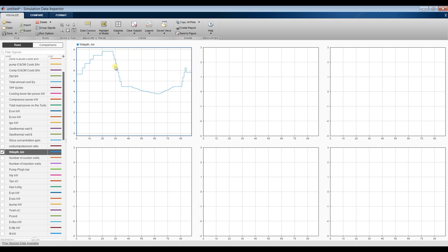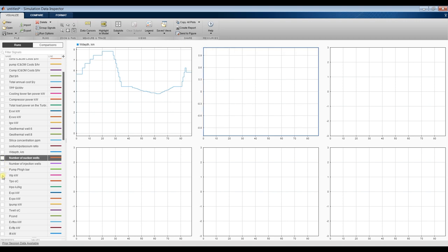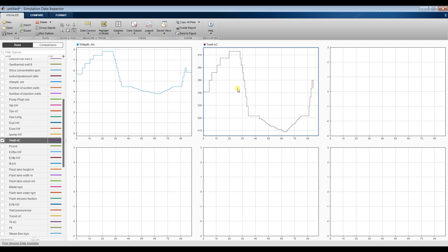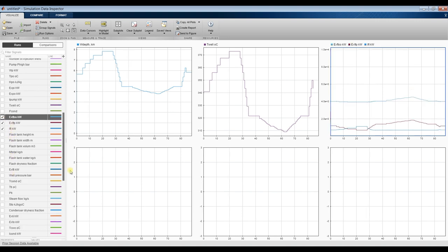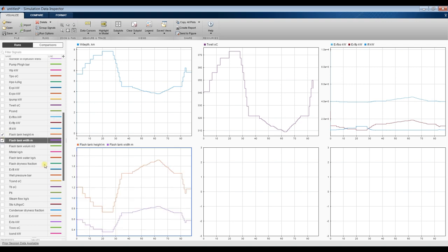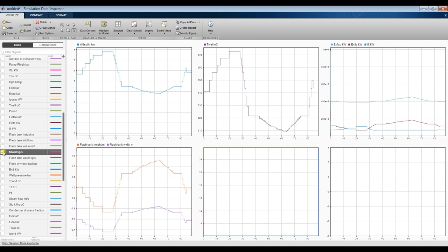Well temperature variation is visible as pressure changes up and down. Also visible is exergy destruction variation and exergy of steam. Let's look at dryness fraction — this is the flash dryness fraction, fluctuating. And this is the turbine dryness fraction — the exit condition from the turbine — normally around 0.88 to 0.89.